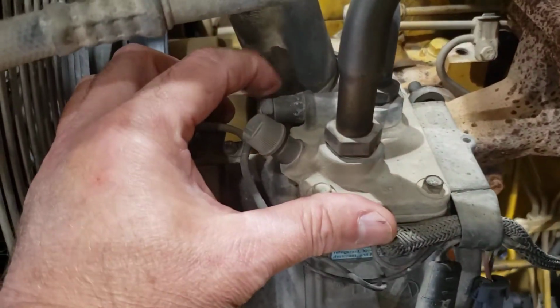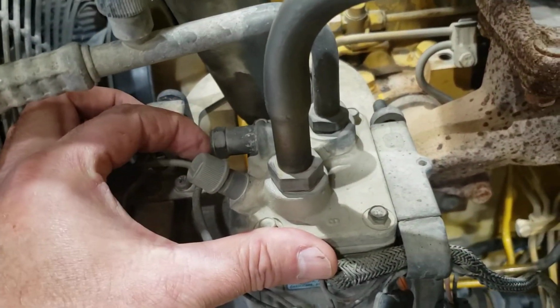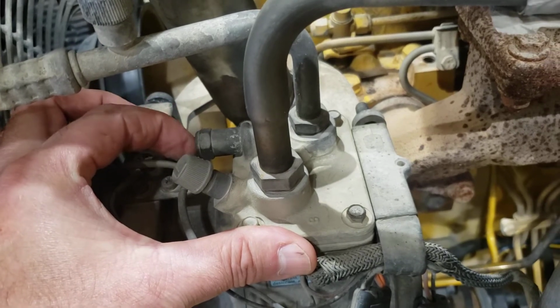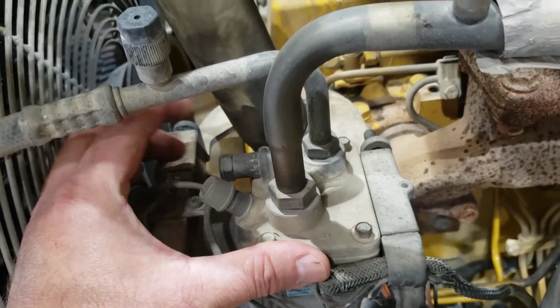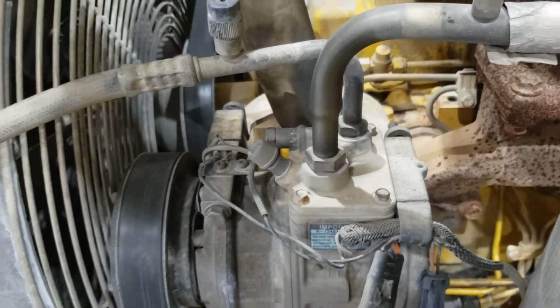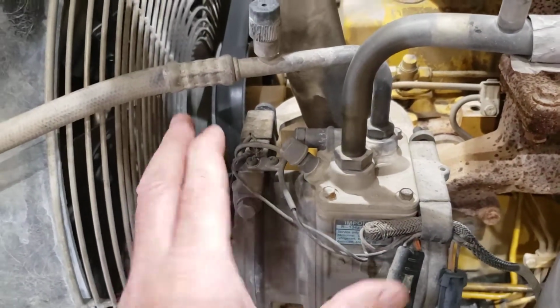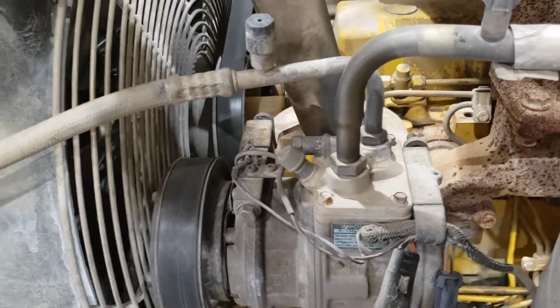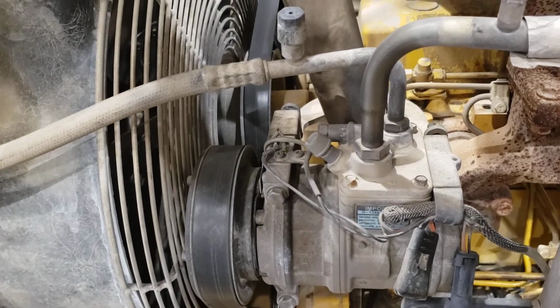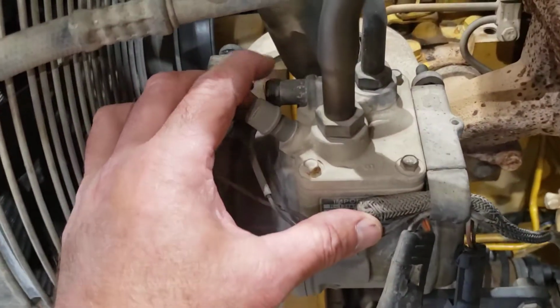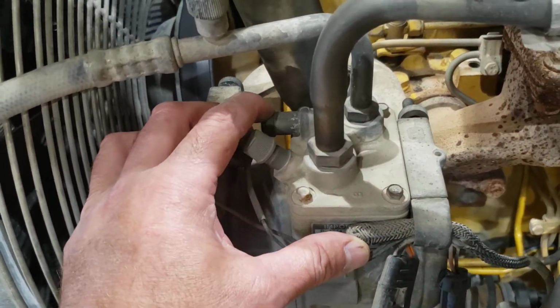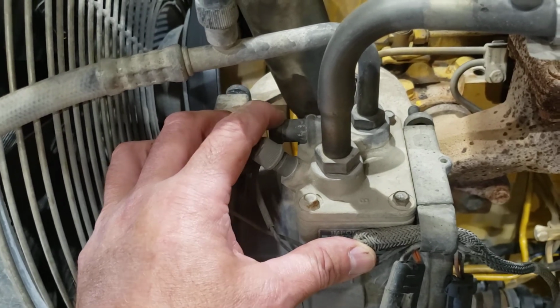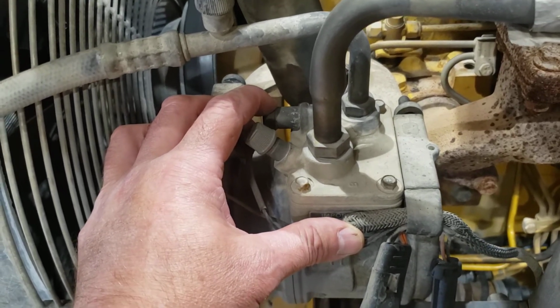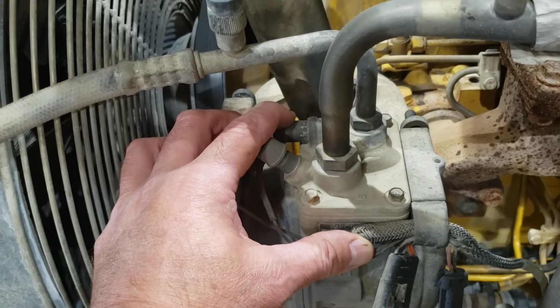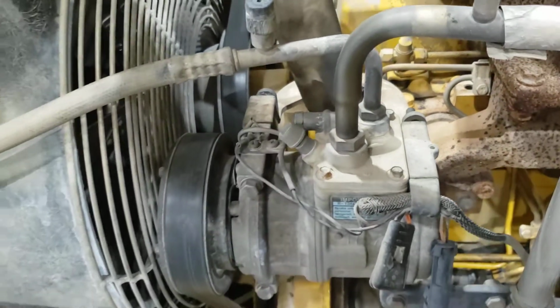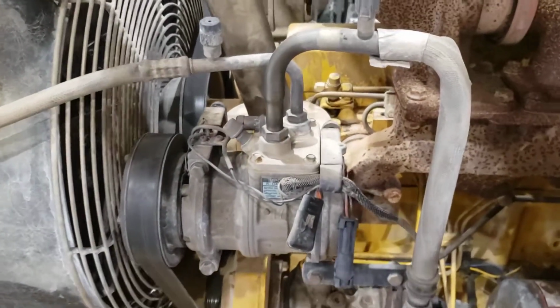On the compressor, it looks like we have a relief valve that would exhaust refrigerant to atmosphere if the pressure got high. For some reason the clutch welded itself together and the compressor wouldn't shut off. That relief valve is there. On some systems you'll find that, and if that relief valve blows out, usually they're set pretty high, like 600-700 psi, but instead of blowing refrigerant at the operator in the cab, it'll exhaust it out here.